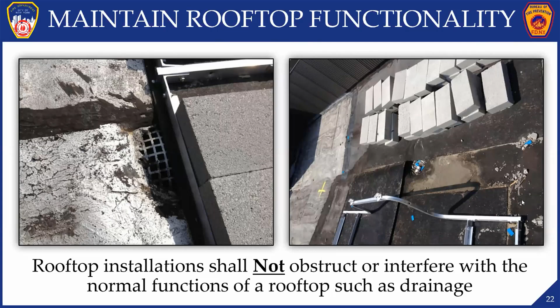Obviously, all your conduits and everything need to be properly labeled on the rooftop. Any conduits or piping closely put together can create obstruction. If they're closely put together and they create an obstruction greater than 12 inches in height or greater than 24 inches in width, they are considered to cause an obstruction to the clear path that they exist in, and they will need to have a non-combustible crossover provided to provide a clear path over them.